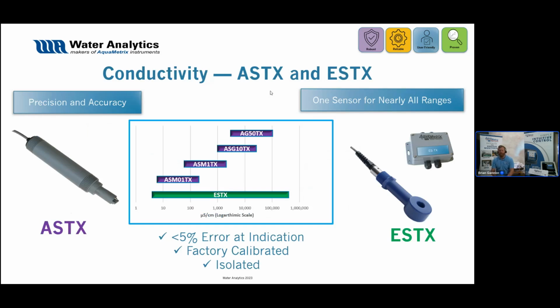And conductivity. For us, we have two different realms of conductivity: our direct contact conductivity sensors with our ASTX, and our wide range toroidal sensors being our ESTX. As you can see here what the wide range of that ESTX is, that's a big advantage. With our ESTX, we did make a design decision to have a blind transmitter box, because in many of these applications the wide range TX sensor needs more space and needs to be more compact. Being able to keep that same look and feel of the sensor, which we believe is very important, it maintains that and then goes to this blind transmitter, but still has all the same values and benefits of the TX line.